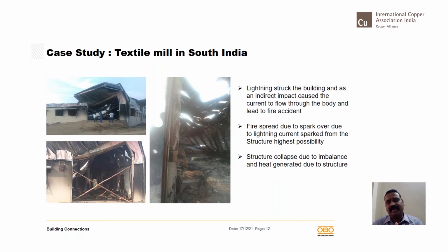Even before visiting this site, I had not seen such a worst accident ever before. What had happened was lightning struck this building just 1.5 meters behind this window on the sheet, which was witnessed by the security guard at about 1 o'clock in the night. This building did not have a lightning protection system. However, they assumed that since metallic sheets and metallic pillars are there, this is going to conduct the current and ground it. Absolutely, yes. If it is properly connected, even the standard permits this kind of usage, which is called utilization of natural components. However, how we do it is very important and critical.